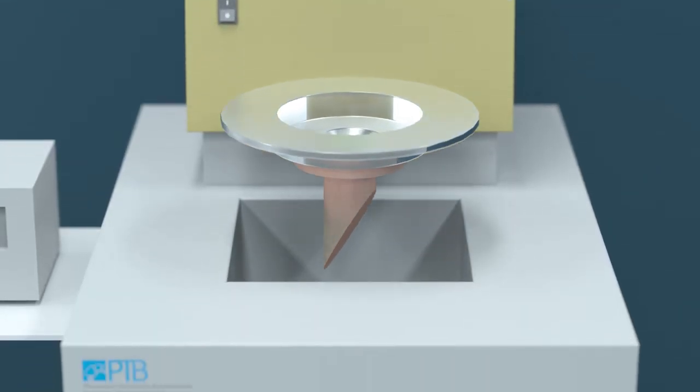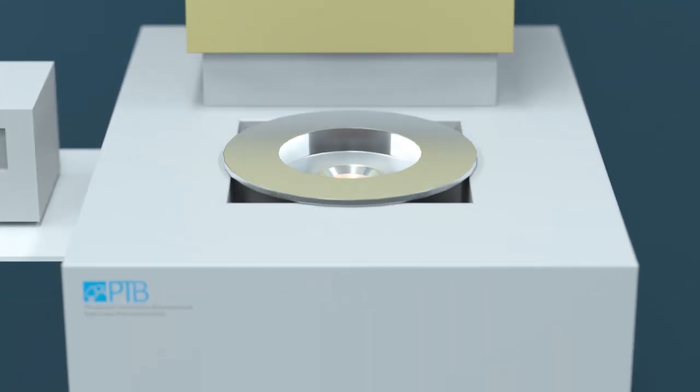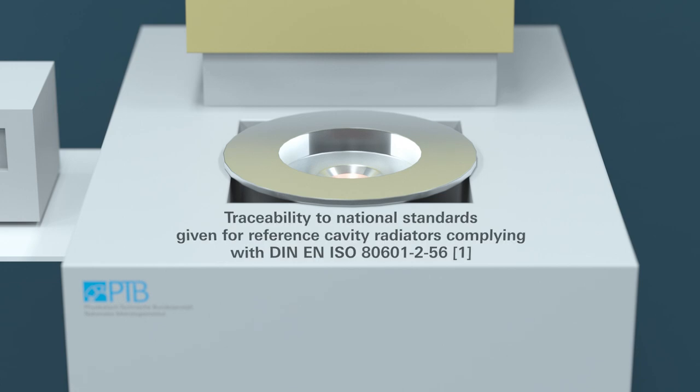If a reference cavity radiator is used according to the recommendation in the applicable standard, the calibration of the reference thermometer is sufficient for traceability to the national standards.